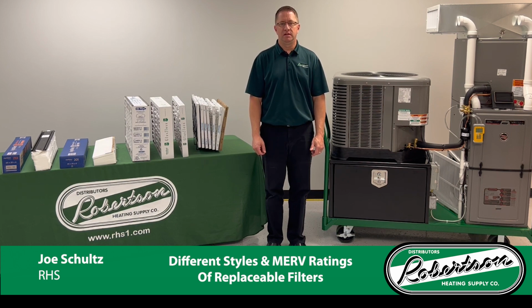Merv ratings of 17 through 20 filter down to particle sizes less than 0.3 microns, which includes everything I mentioned before, plus viruses, carbon dust, and combustion smoke.